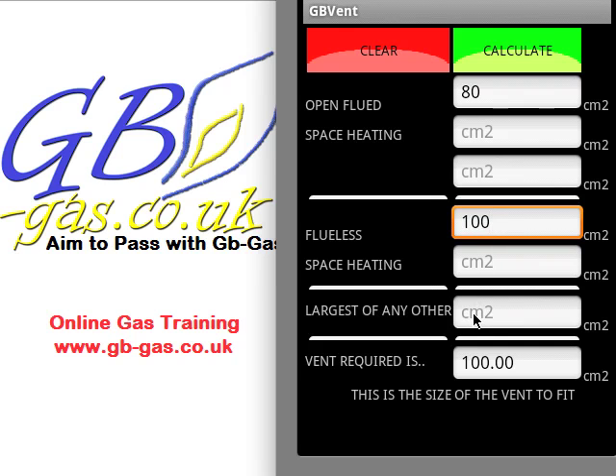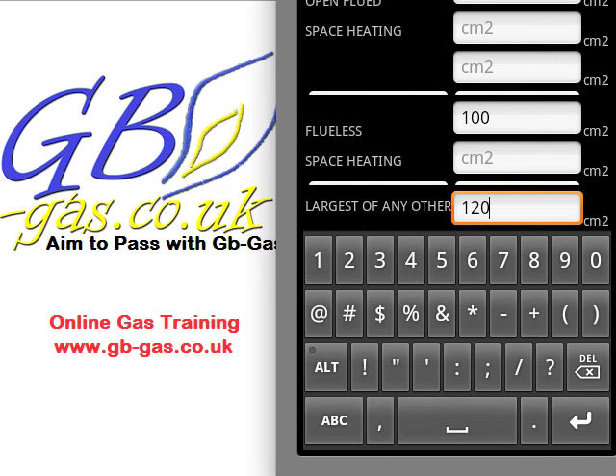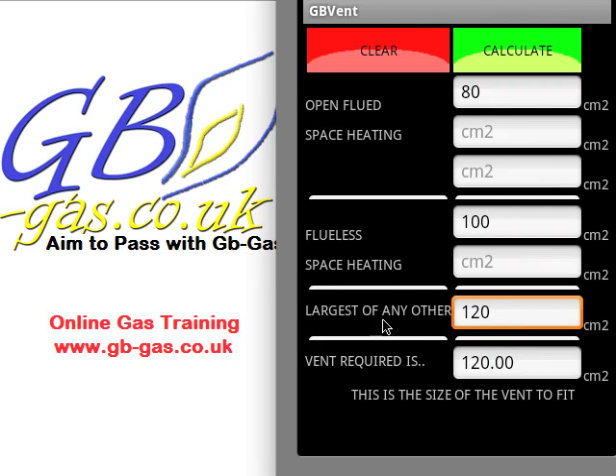If I had a water heater in the room — which is not space heating, and it might be the largest of any other appliance — we might require 120 cm² for this, so we type in 120 and hit calculate. In this scenario, where I have an open flued boiler and gas fire, plus a flueless gas fire, plus a water heater, the water heater wins because it needs 120 cm² worth of ventilation. It's always the largest between the three rules: open flued space heating, flueless space heating, or the largest of any other appliance.